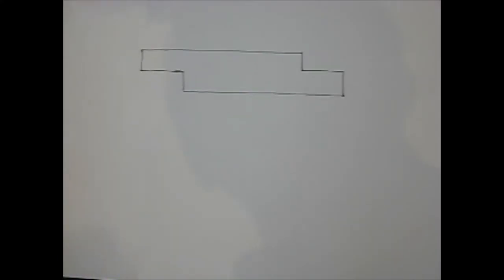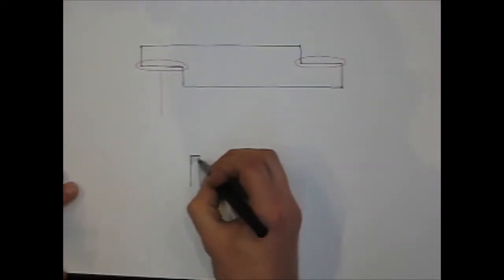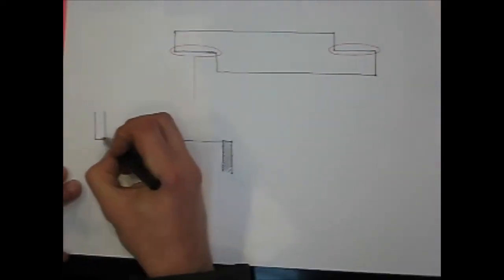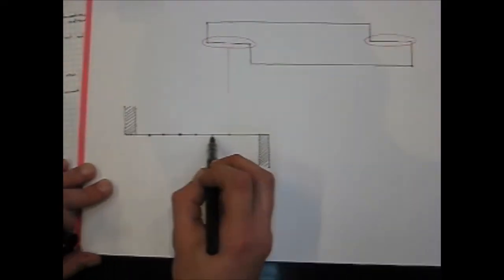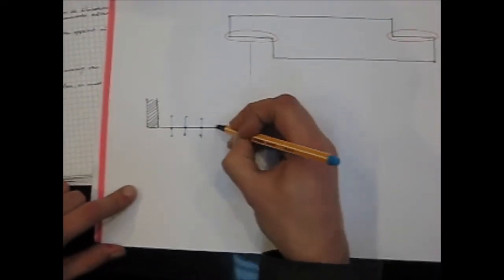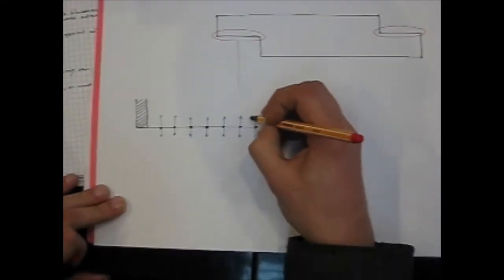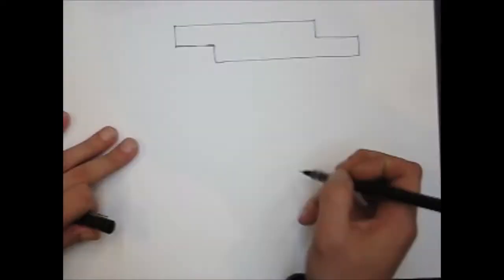One of the main climate problems EWI has is thermal bridges. They're located on the single facades, where the volumes are offset. Here, the thermal bridges are formed by steel columns that are in direct contact with window frames, without proper insulation.